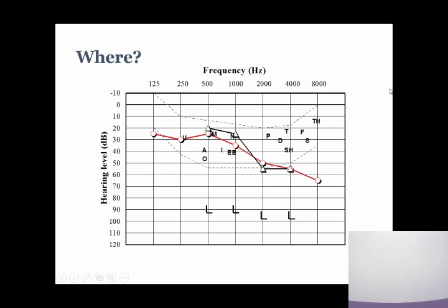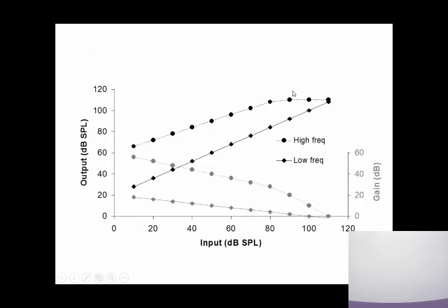So what is the answer to that? Not linear amplification of everything, but to put it into bands. And every hearing aid that you buy these days actually comes with bands, any number between 4 and, I don't know what the upper limit is, 12 or something like that. And there is an amplification in each of these bands. For the low frequencies you have little amplification, for the high frequencies you've got more amplification, and obviously the exact slope of these you can set in a fitter.